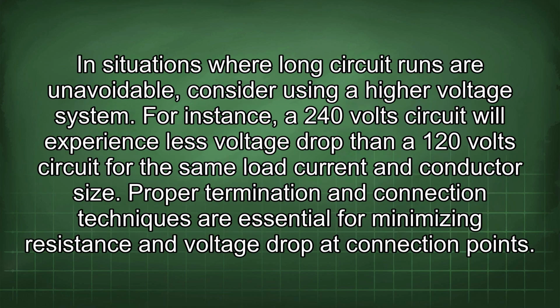In situations where long circuit runs are unavoidable, consider using a higher voltage system. For instance, a 240-volt circuit will experience less voltage drop than a 120-volt circuit for the same load current and conductor size.